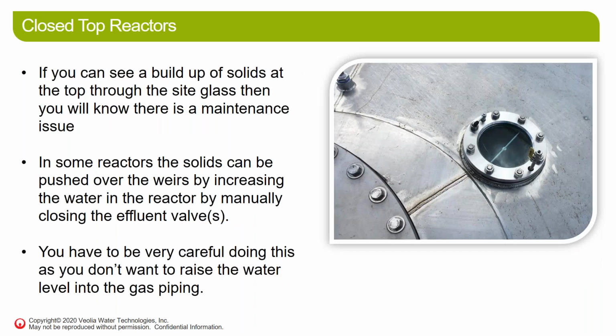So typically we have a viewport somewhere on the top of these closed top tanks. If you're seeing issues with your performance, seeing solids loss, the first idea is to go look in the top, see what you can see. It's always very difficult to see in there because it's dark, and sometimes you can't get good access to that viewport. But typically what I've been able to see is, if I take a jacket and completely enclose myself around that viewport and look inside with a nice strong flashlight, and you hide all the daylight away from it, you can see. So that's really the first way you can look and see if you have some kind of maintenance issue that you need to address.